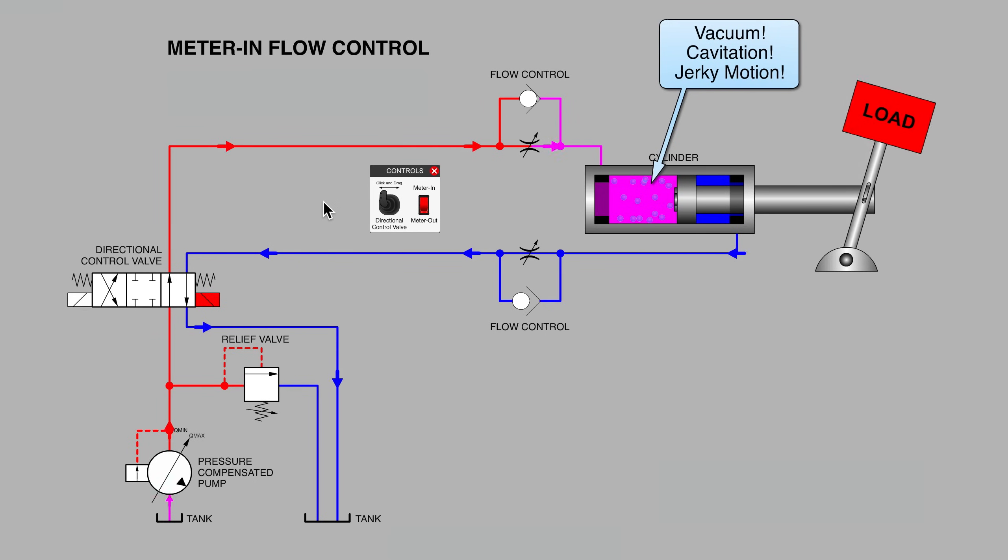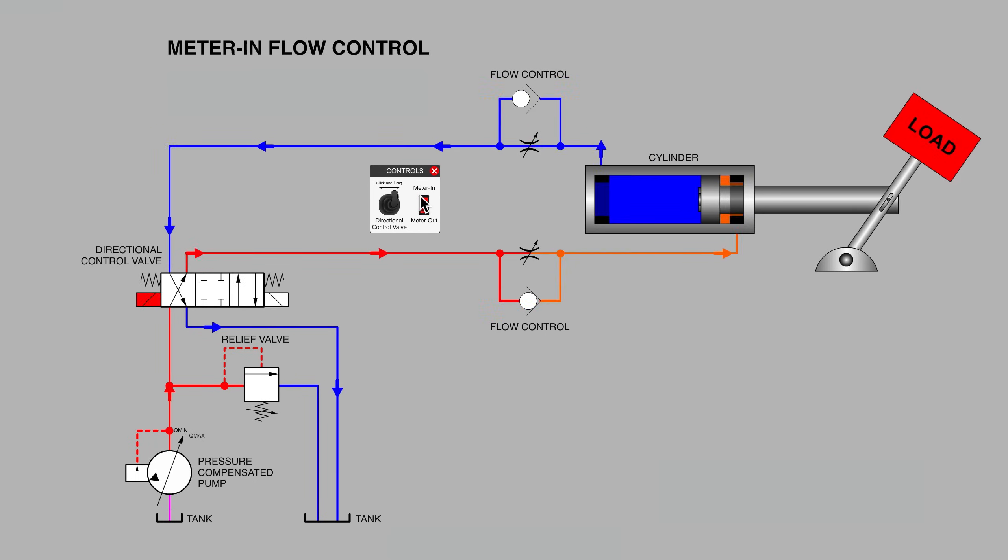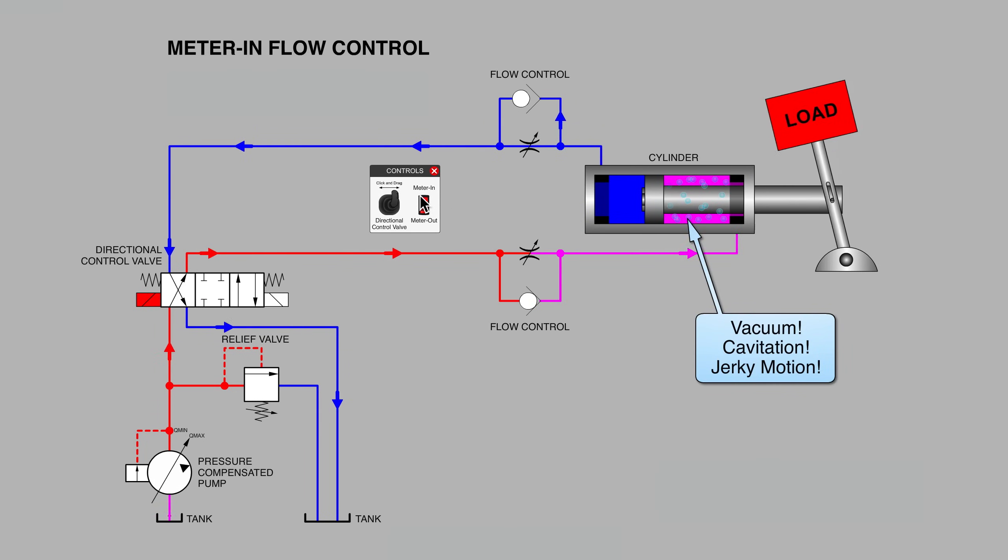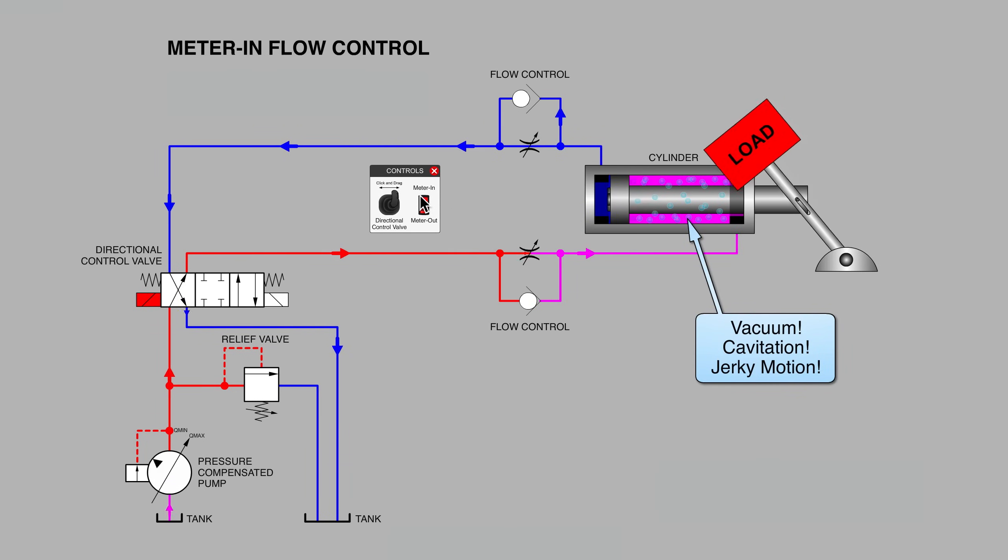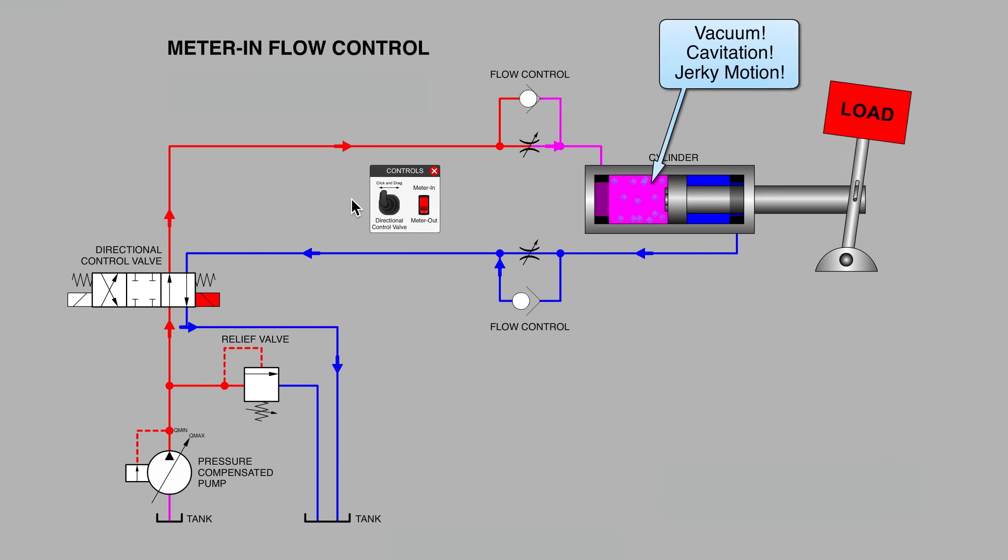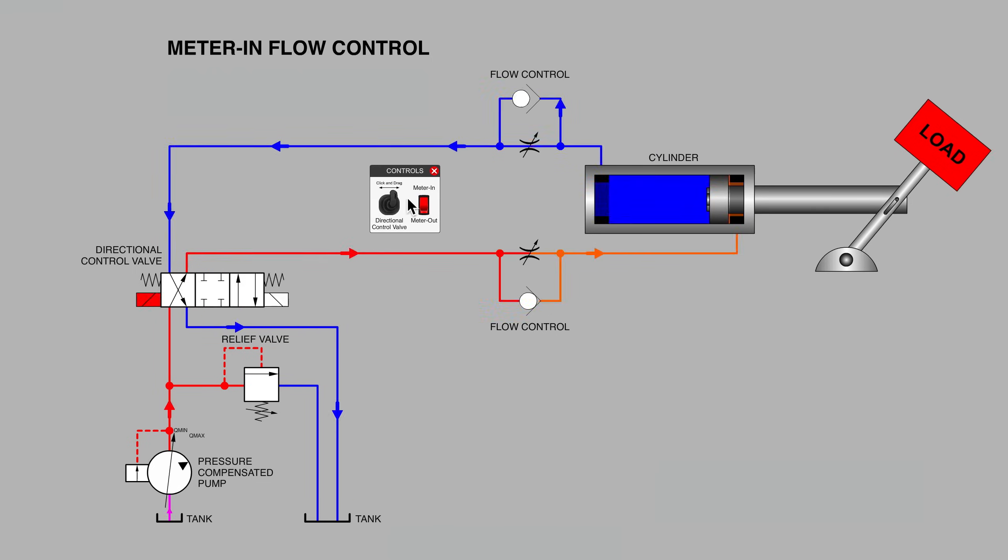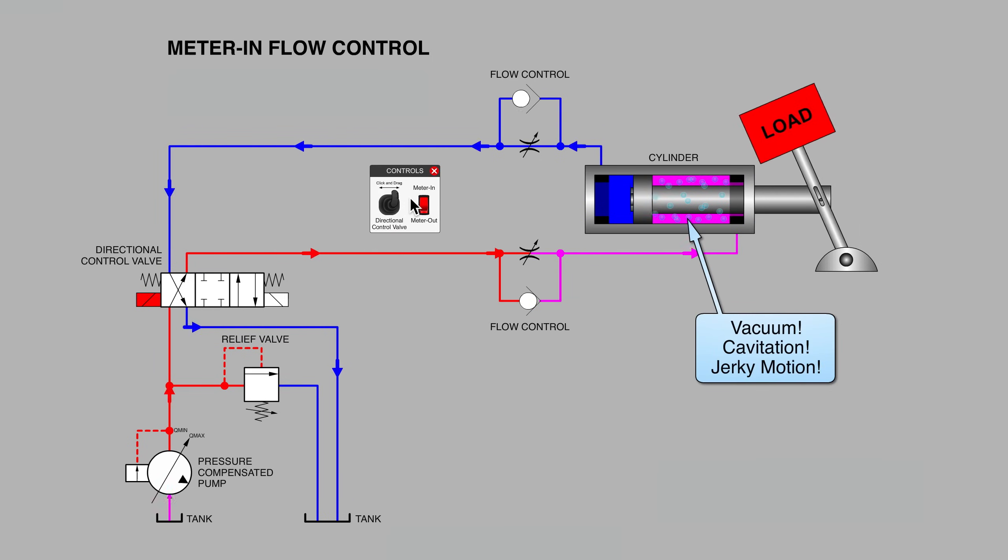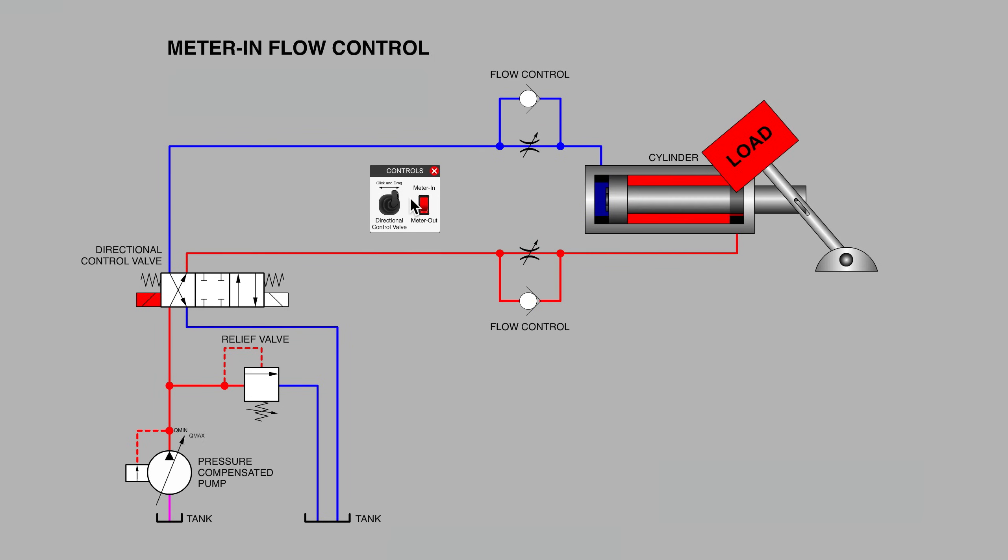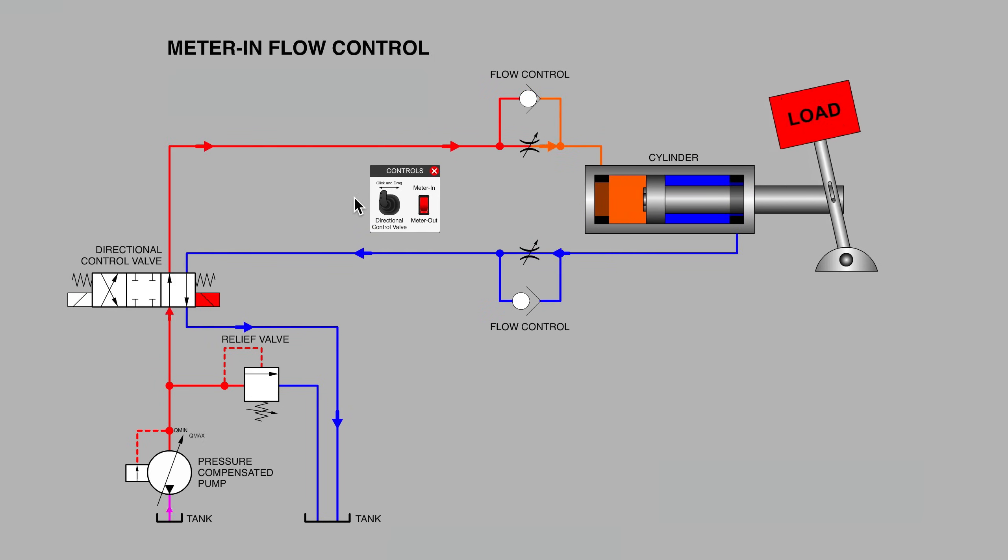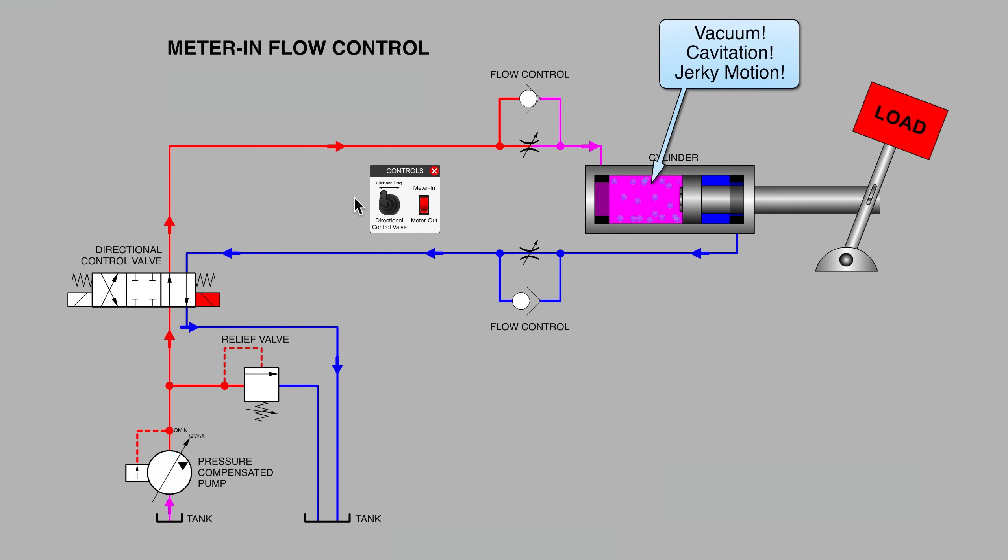Now, of course, what's special about this particular arrangement is that we've got a load that runs over center. That pendulum overrunning load is a handy one in these animations for understanding what the effects of a runaway load, sometimes referred to as a negative load on a cylinder, might do to various parameters of the hydraulic system. In this case, we could tell that not all is well with the meter in scenario.